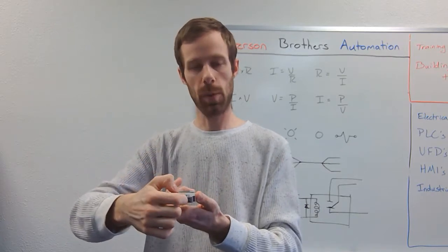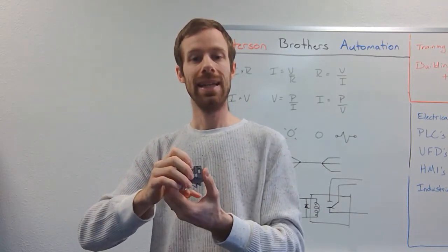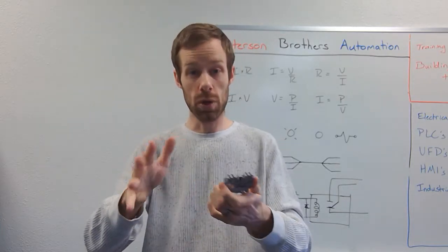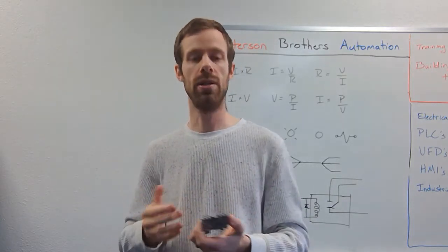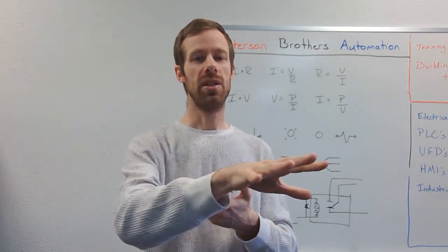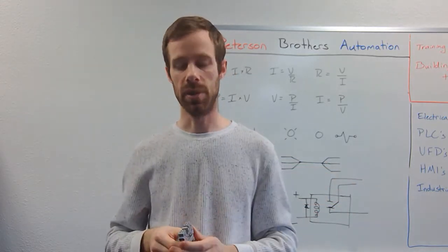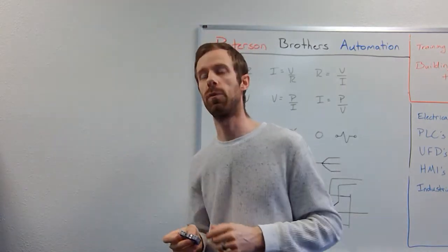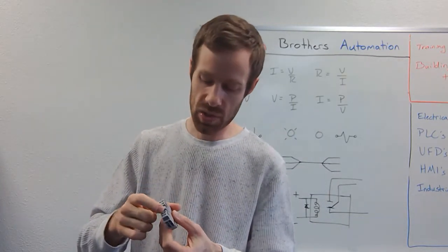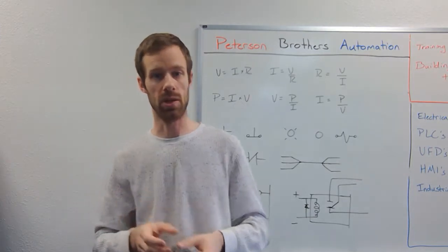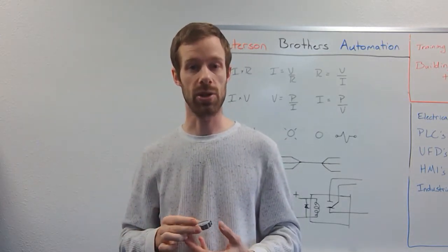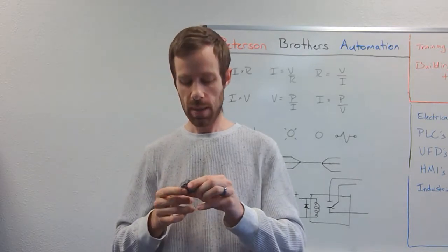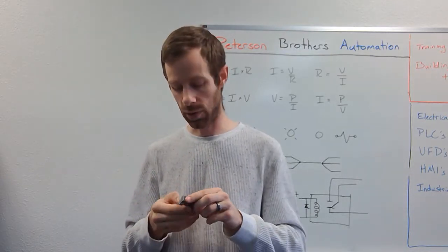This set of 2 terminal blocks jumpered together gives me all 7 of the wires that I need to distribute, which is why we call it distribution, to distribute the power to the other 7 load devices that are required. So this is a screw down terminal block, and we have to be aware of proper torquing, because when this is tightened down to the appropriate torque level, it withstands vibration. So even if the machine is vibrating, this does not work itself loose because we've followed proper torque specifications.